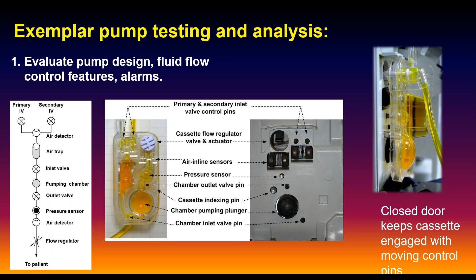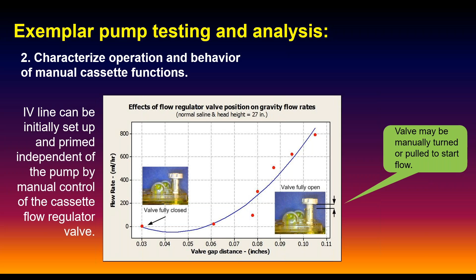They used the disposable cassette that the pump, when it was properly used, the door was properly closed, would engage these solenoid pins that would control the flow of the fluid through the pump. Incredibly good. When I also did some testing on the pump itself, it had a real sweet little feature. On the cassette, they had a little valve that the nurses could use to prime the pump. So it worked like a little needle valve. You could set a flow with a little needle valve, or you could pull it open. It only took a fraction of an inch, 1/10 of an inch or so, to be fully open. So it was very convenient for the nurses to prime the pump. Very good design. But when you put the cassette in, the pump took control of that valve.